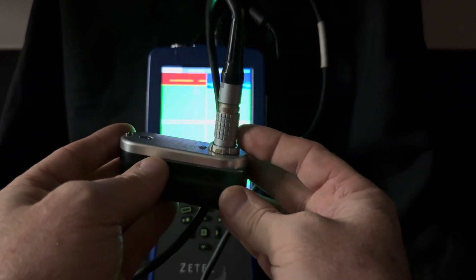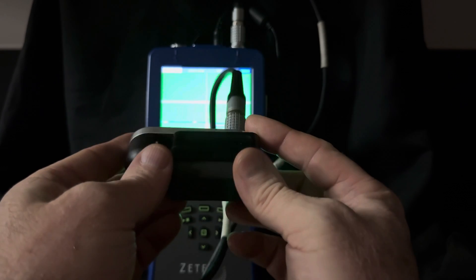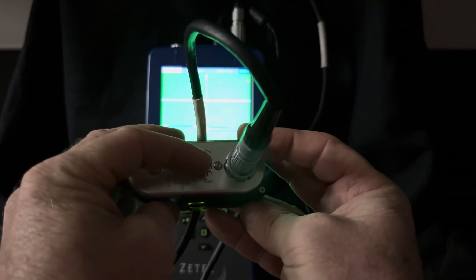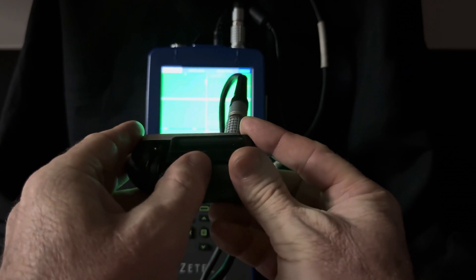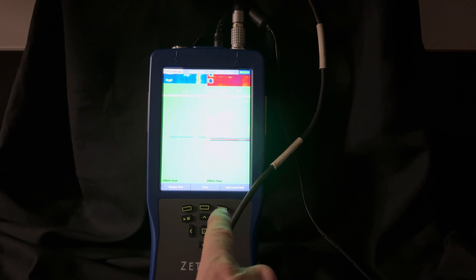If I'm looking at the probe from the top, conveniently Zetec, which has been around for 50 years, lines up perfectly with that center line. I don't know if that was by design or not, but it's going to help me stay right in between my rows of rivets.